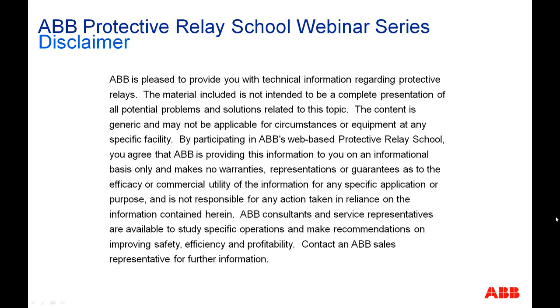There is another question, how to compensate the inrush current to prevent the false tripping of line differential. Yeah, so the inrush current is characterized by the second harmonic, and all the differential protection relays filter out the second harmonic, and then block the tripping as we discussed during our presentation.